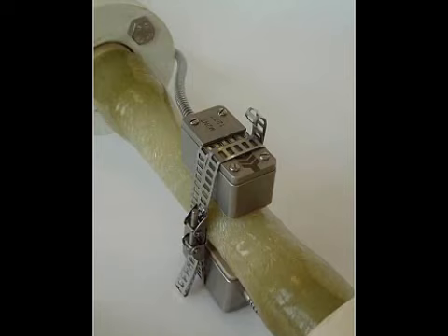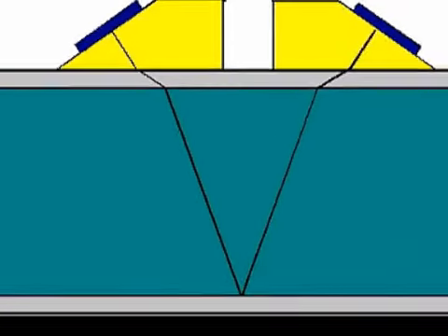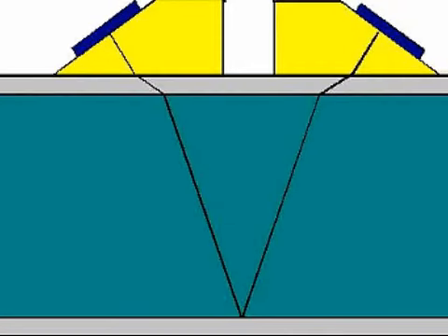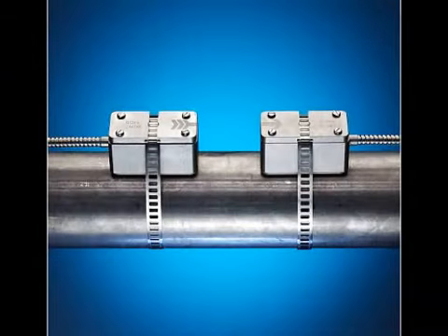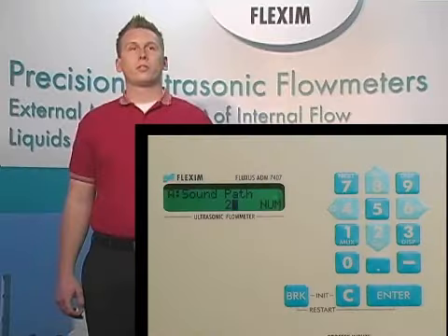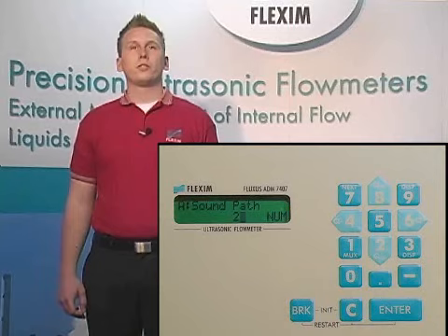The more preferable way to mount our transducers is in what we call reflect mode, or two sound paths. In this mounting system, the sound goes through the fluid twice, bouncing off the opposite wall of the pipe once, and we mount our transducers on the same side of the pipe, one several inches downstream from the other. This has several benefits, not the least of which is that it's physically much easier to get proper placement and access to the transducers like this. You can watch video number 4 for more information on how to install our transducers on a pipe. For now, let's choose two sound paths or reflect mode and hit enter.